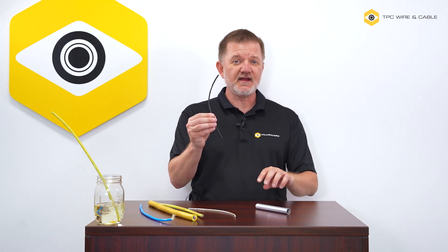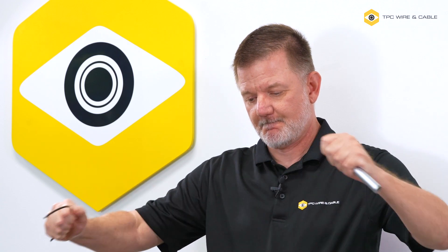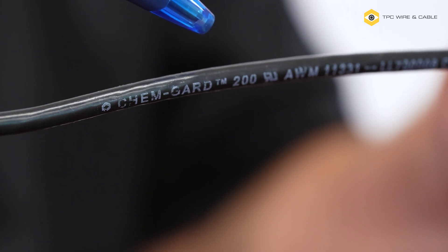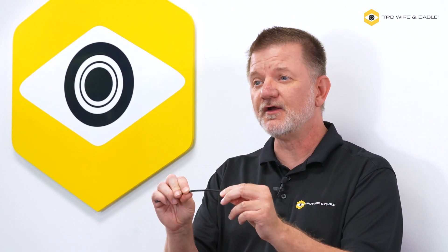Let me do the same thing now with a piece of 10-gauge single conductor Chem-Gard — and I'm not going to stop at just scraping it twice; I'm going to do it multiple times. Even after many passes through the conduit, you'll see that the Chem-Gard is undamaged. The fluoropolymer is very tough. Even if it were to be nicked, it would simply expose more fluoropolymer underneath, because the protection goes all the way through.